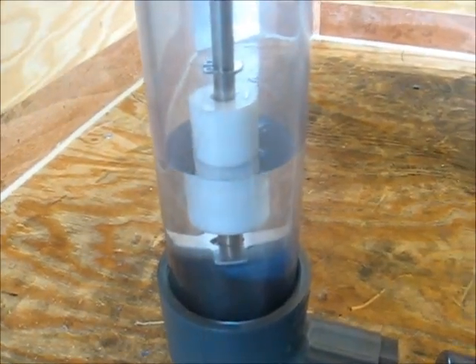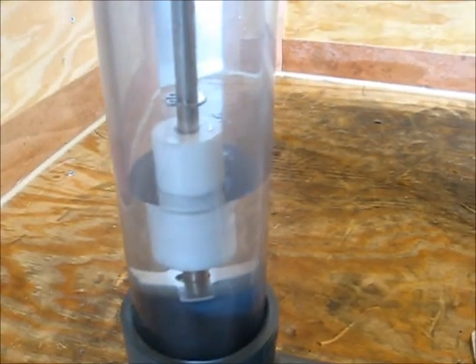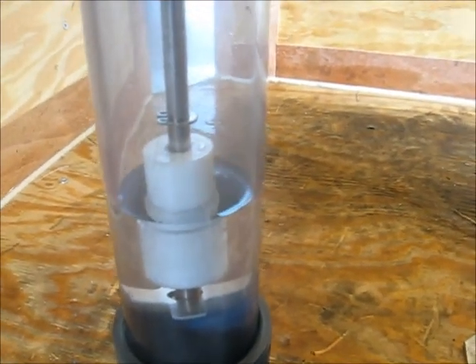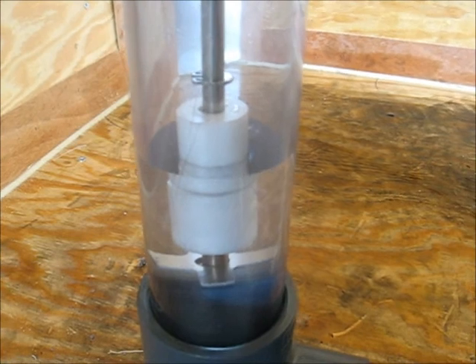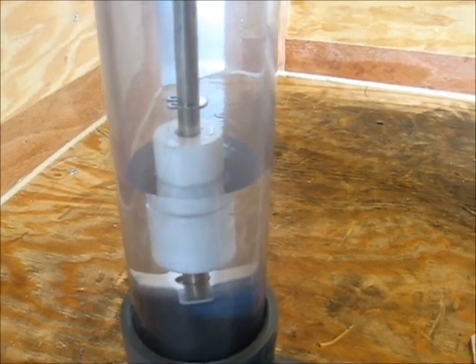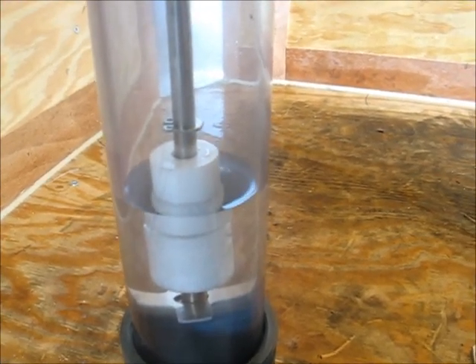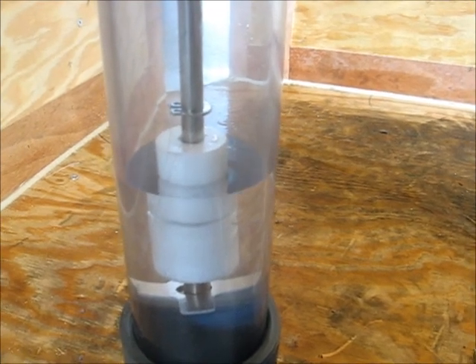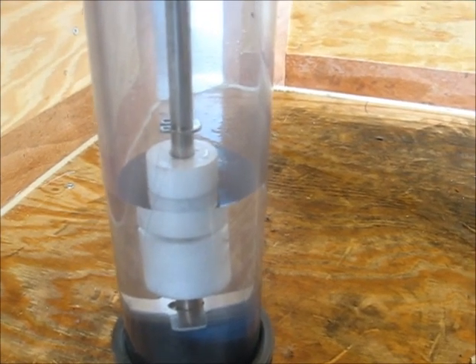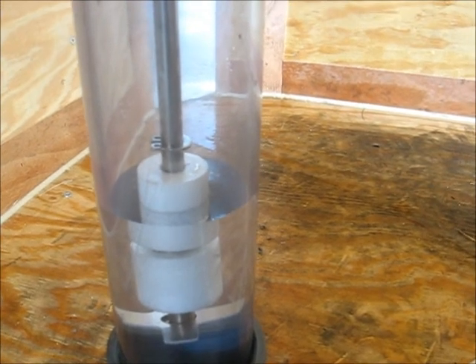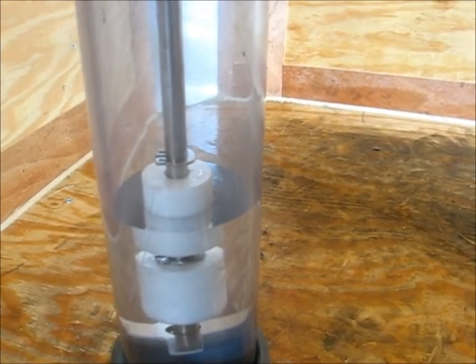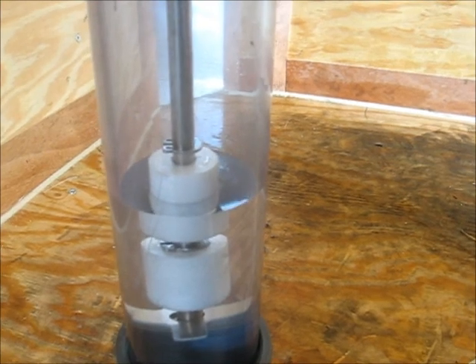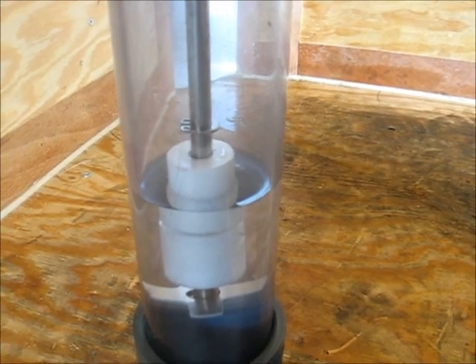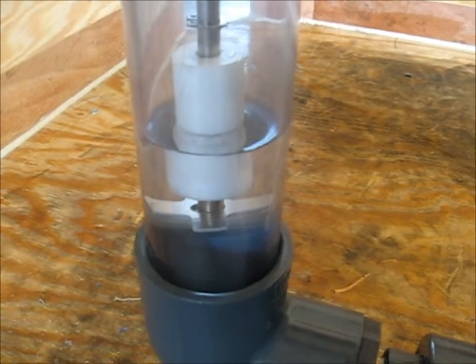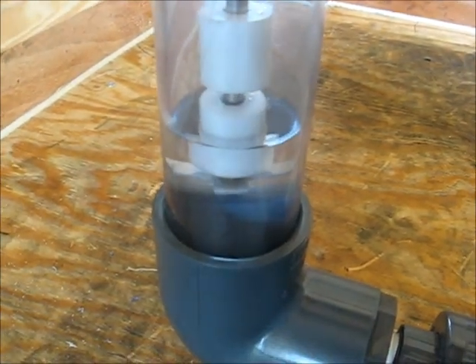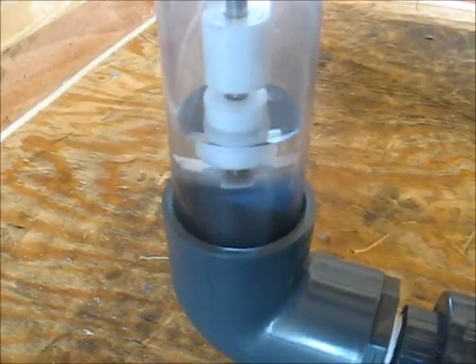Filling the knockout tank up with water. What we want to see is that the pump cuts on when this float reaches. Should happen in just a couple of seconds. There it is. You hear the pump cut on. It's pumping the water out. See the water pumping down? The pump cut off.